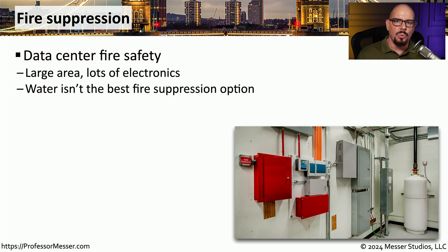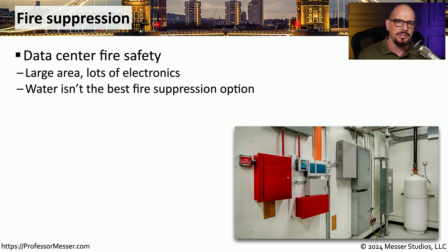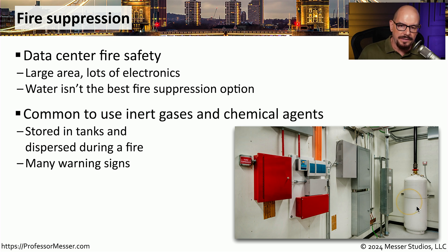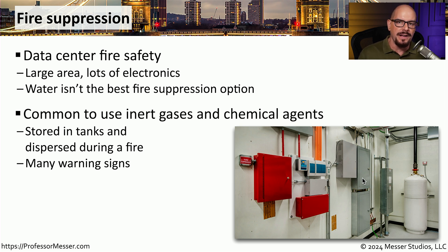Normally, we would use water to control a fire. But in an environment such as a data center, when you have this much electrical equipment, you'll want to use other means for fire suppression. If you were to look into the back of the data center, there's probably a tank that contains some type of inert gas or chemical agent designed to either suppress the fire or remove any type of oxygen from the air.